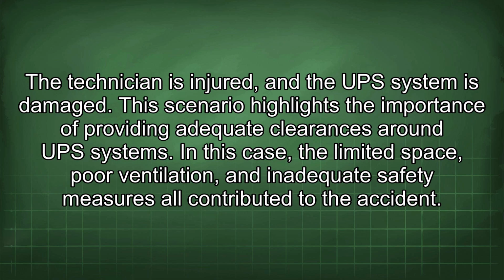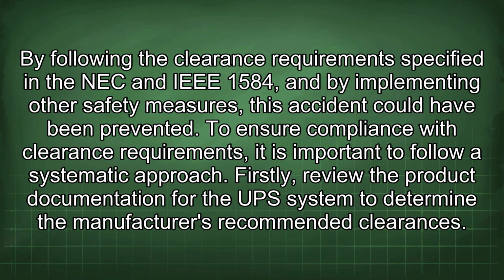This scenario highlights the importance of providing adequate clearances around UPS systems. In this case, the limited space, poor ventilation, and inadequate safety measures all contributed to the accident. By following the clearance requirements specified in the NEC and IEEE 1584, and by implementing other safety measures, this accident could have been prevented. To ensure compliance with clearance requirements, it is important to follow a systematic approach.